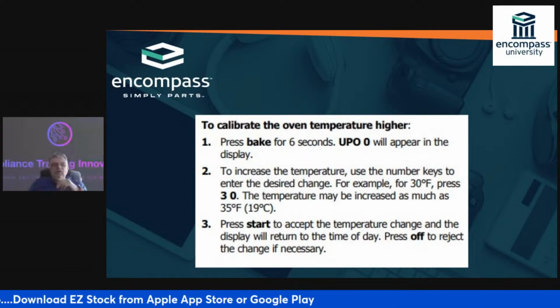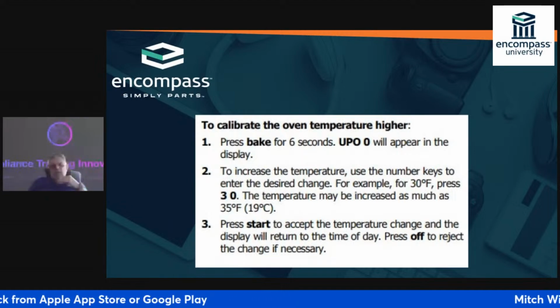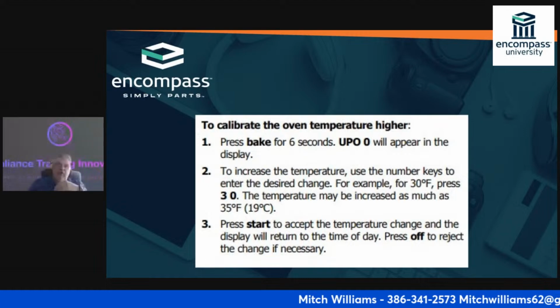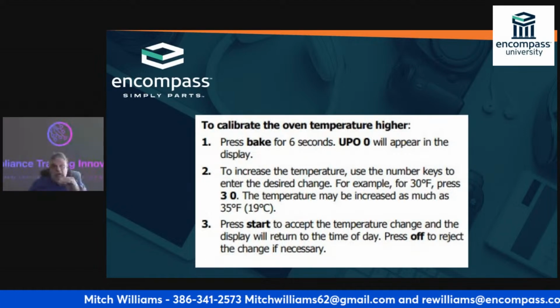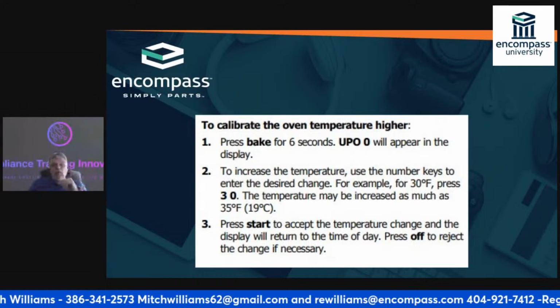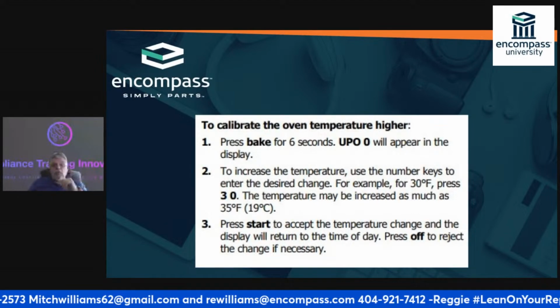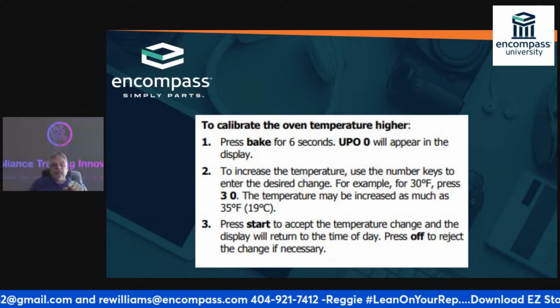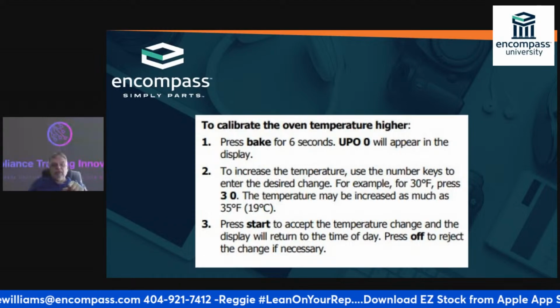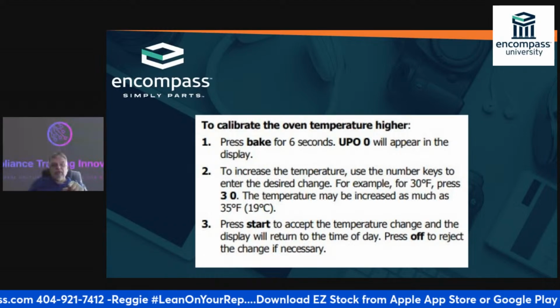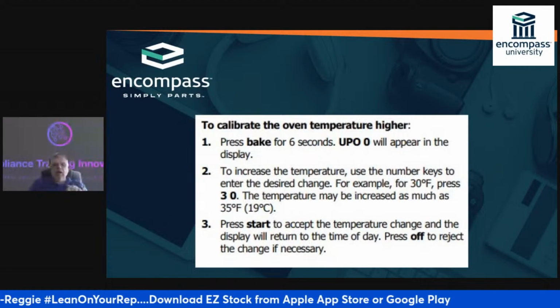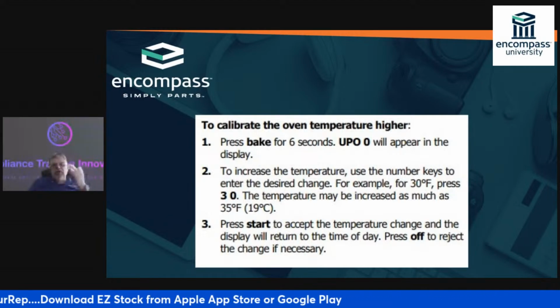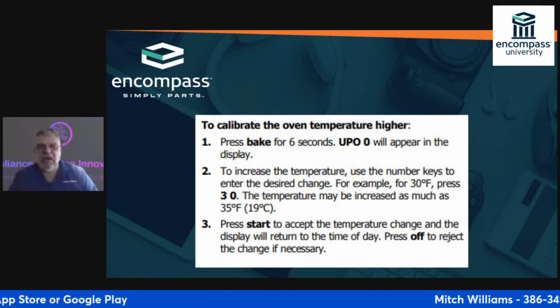The temperature may be increased as much as 35. You can't get any higher than 35 degrees. If it's any higher than 35 degrees, you're going to have to replace either the thermostat or the board, depending on which one is the problem. After you do that, you press start, and it will accept the temperature change in the display, and it will turn back to the time of day. Once I get done, I'll press off to reject the change if it's not right.